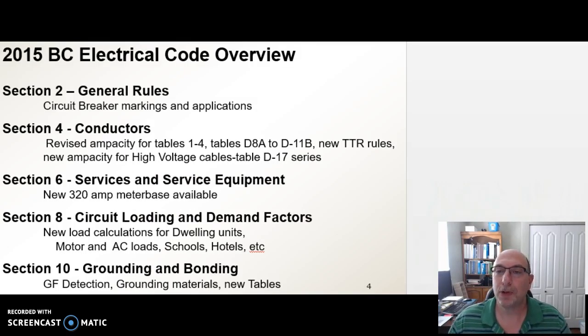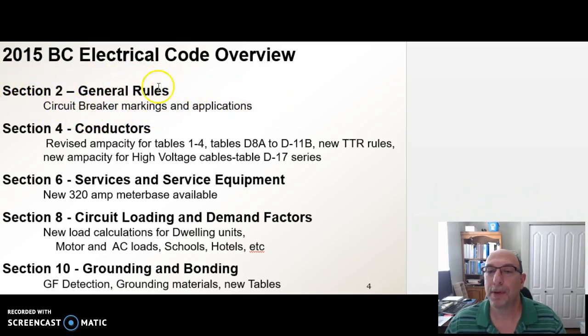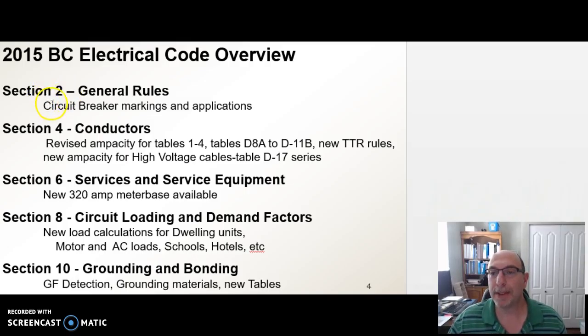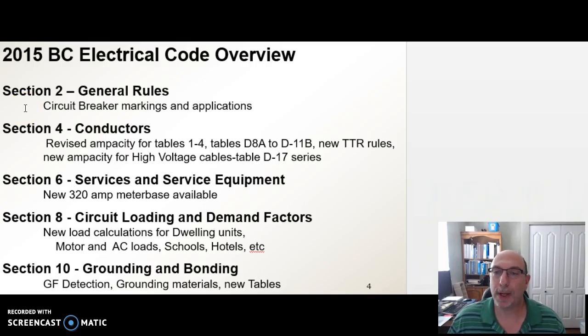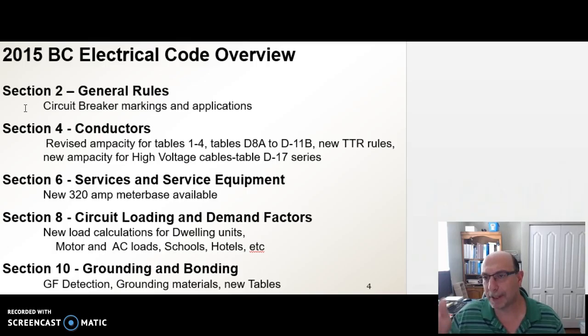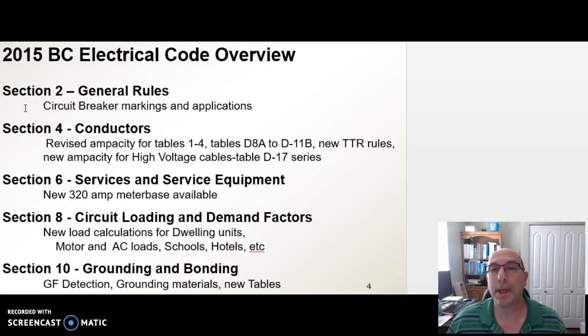Now let's get into the changes for the 2015 Canadian Electrical Code. In Section 2 — the general rule, which pertains to any section in the code — the big change is circuit breaker markings and application. Circuit breakers have to be marked with a slash rating. If you're using a circuit breaker on a 120/240, 347, or 600-volt service, the breaker must be marked 120/240 or 347/600. If you're using a circuit breaker on a delta system, which is an ungrounded system, they must be marked 240, 480, or 600 volts — you must see the phase-to-phase characteristics on that circuit breaker.